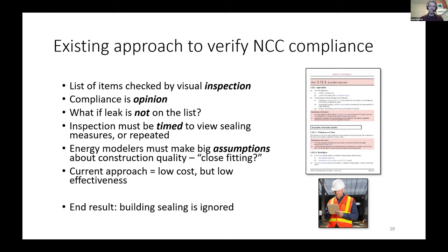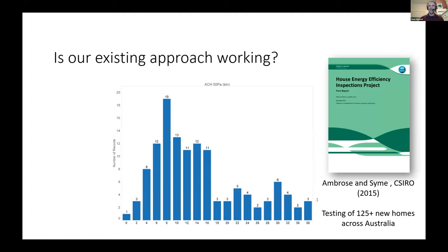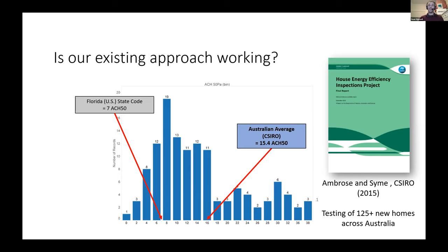Well, if you just look at the data from CSIRO, for example, no, it's not working. The Australian average is 15.4 air changes per hour, out of 125 plus homes that they did a few years ago. That's bad. Just some numbers for comparison. Florida, US state code, one of the least stringent in the US, 7 air changes per hour. So that's twice as tight as that. That's the code. That's the worst you can do and still get your certificate of occupancy. That's the worst.